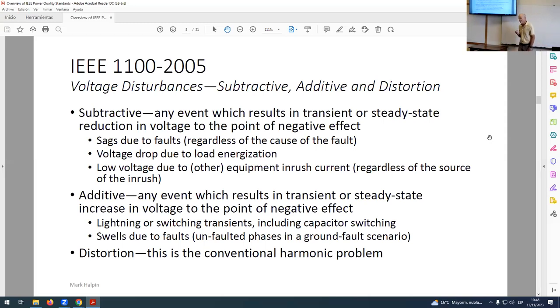In the Emerald Book, voltage disturbances are considered to be one of three kinds. There are voltage disturbances that are additive. Those tend to be overvoltage transients like lightning and switching surges. There are voltage disturbances which are subtractive. They tend to reduce the supply voltage. Those are disturbances like sags.